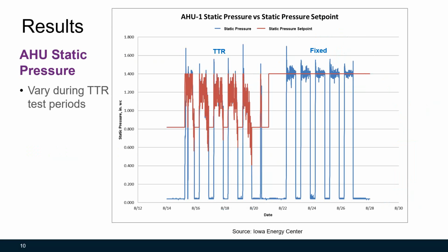Let's first take a look at static pressure versus static pressure set point for both the fixed static pressure control method and the tier trim response method. The blue lines represent the air handling unit static pressure, and the dark red line represents the static pressure set point. First, we ran a week of tier trim response method, then we ran another week of fixed static pressure control method. We can see that during the week of implementing the tier trim response method, both static pressure and static pressure set point varied. The range was from 0.4 inch water column to 1.4 inch water column. During the week the fixed static pressure control method was implemented, both static pressure set point and the static pressure did not change much, staying at around 1.4 inches.